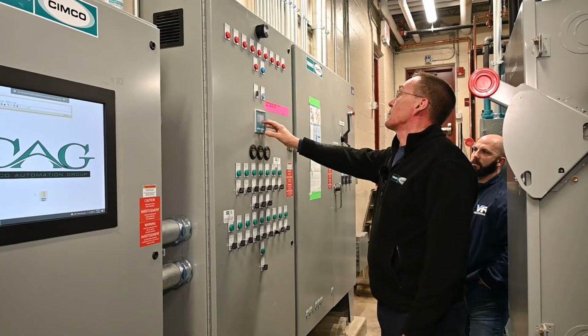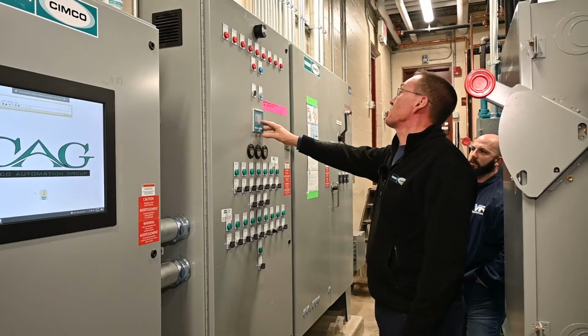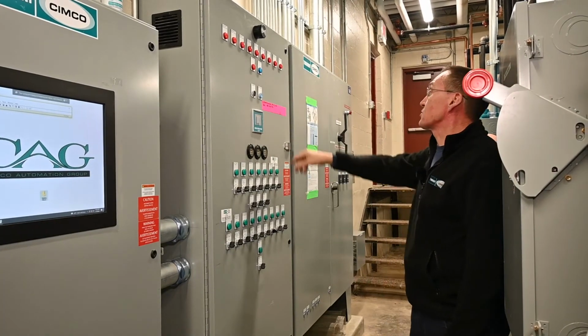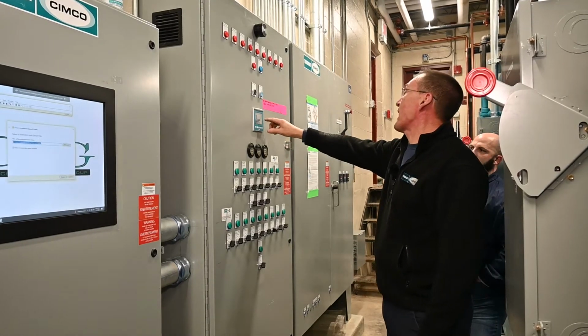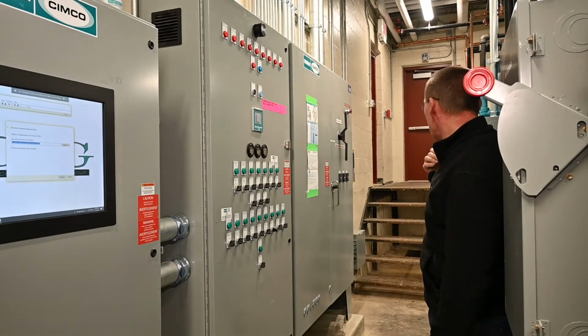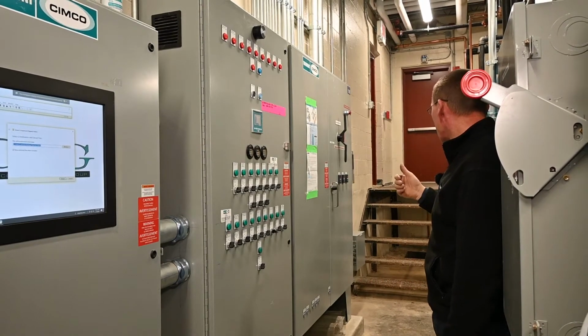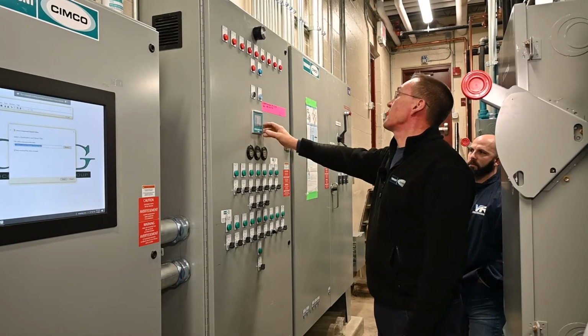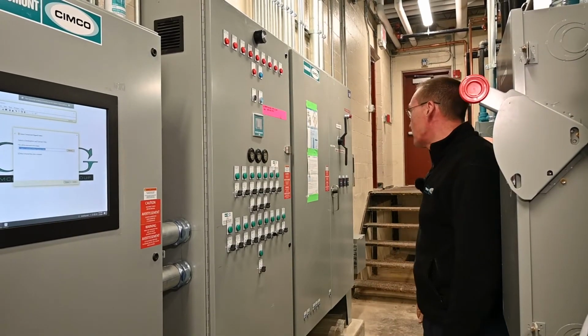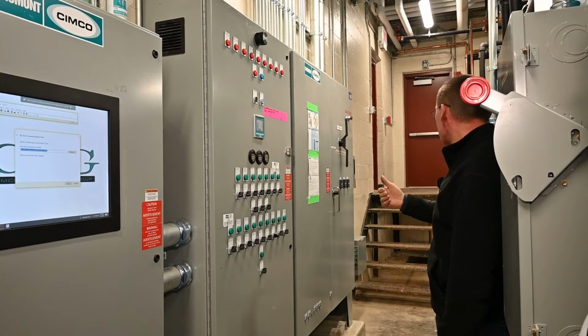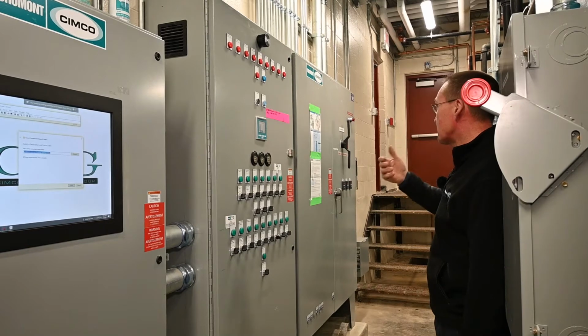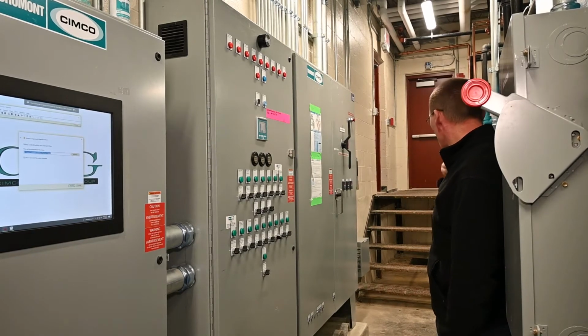Oil filter fault, that doesn't come into play here. And then compressor loaders. If you happen to be watching that screen when a compressor first starts, you'll see these lights change in pattern as we load the compressors based on 25%, 50%, 75%, and then 100%. At 100%, CR4 is lit, stays lit for 10 seconds, and then shuts off for 10 seconds. That's an internal Bitzer compressor thing that keeps the compressor at 100% load. All right. Back from there.